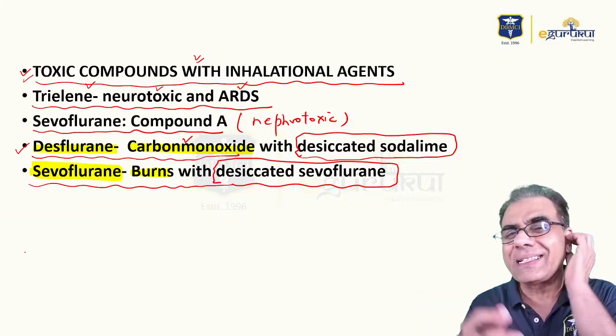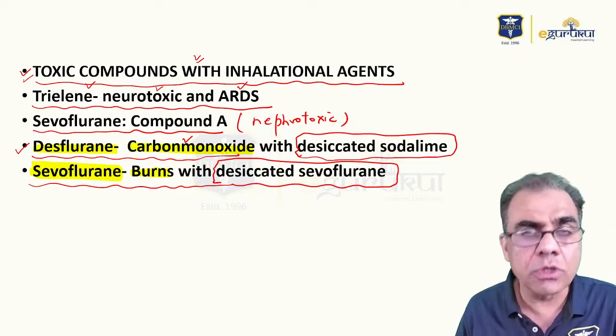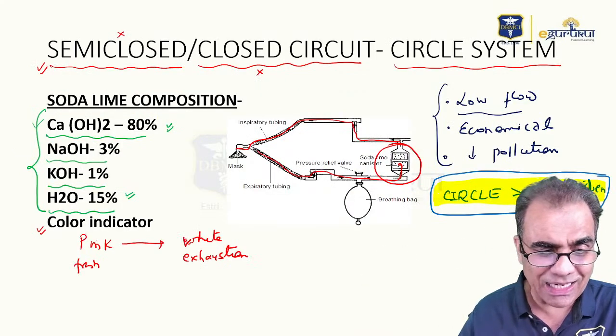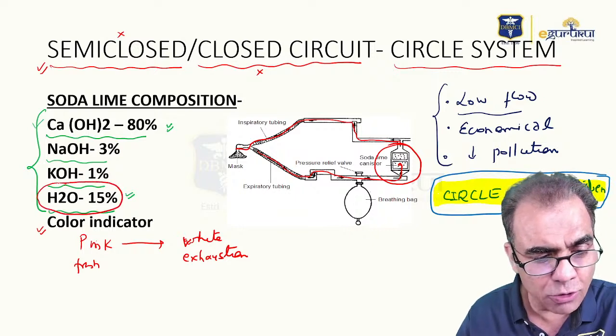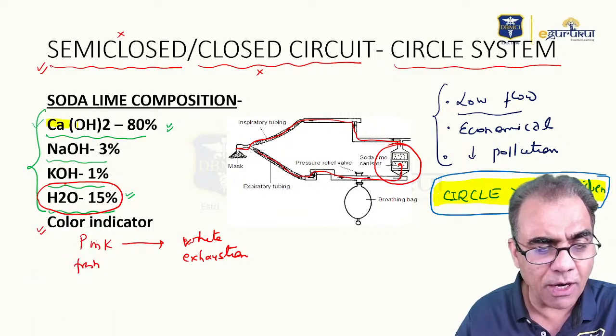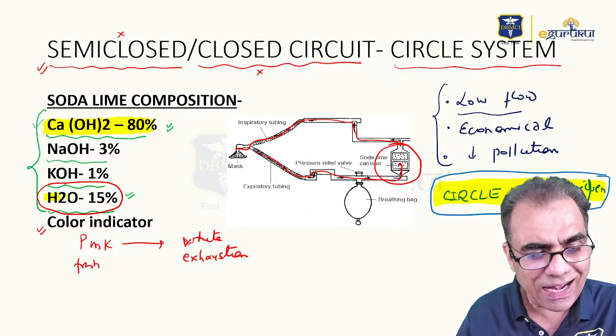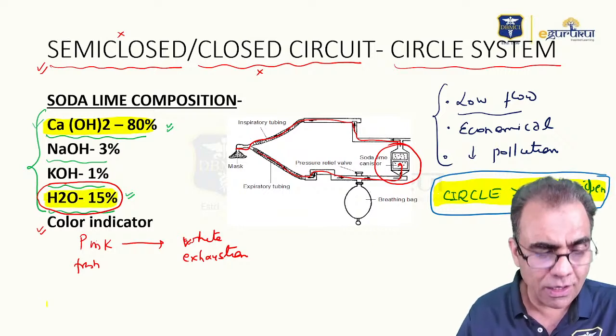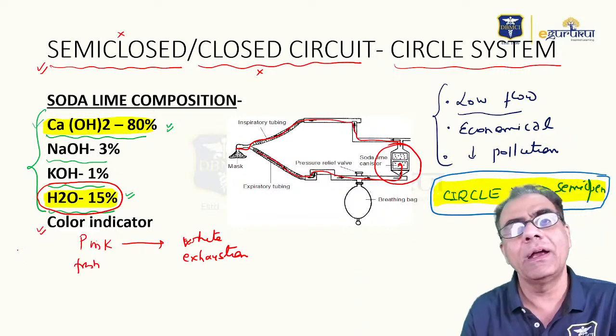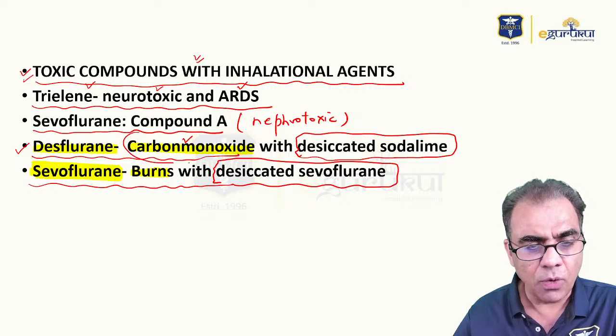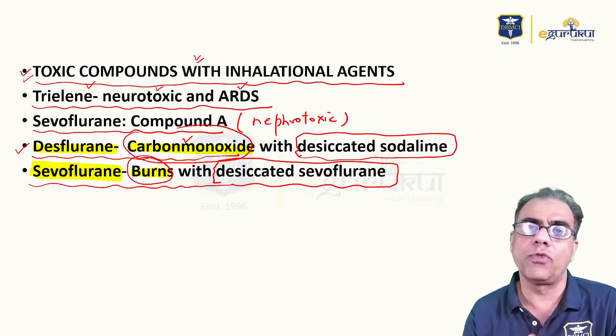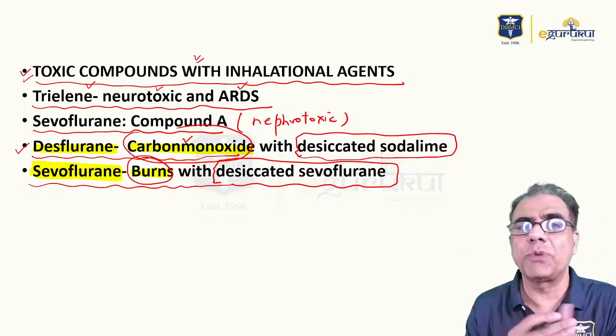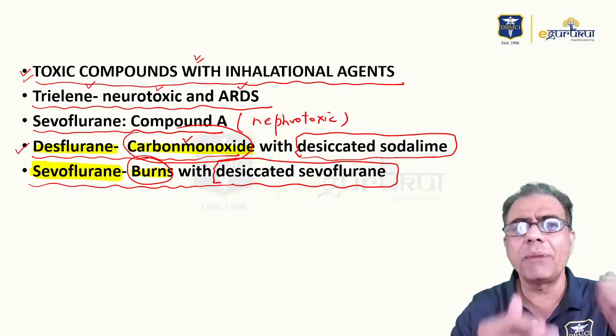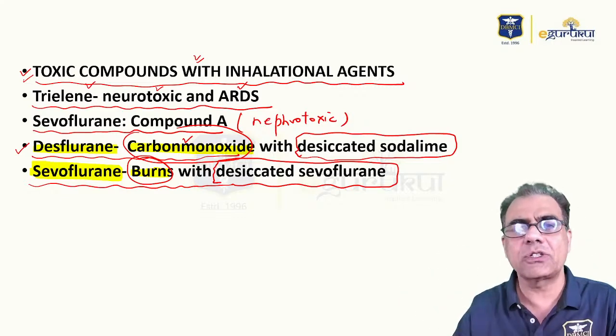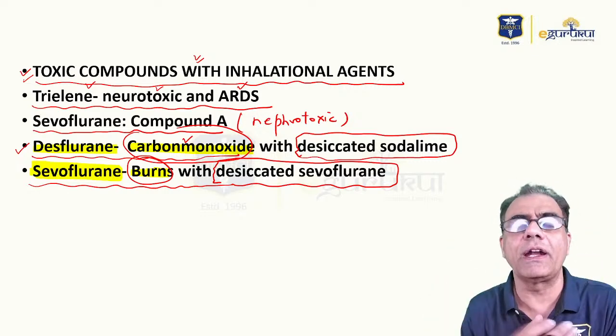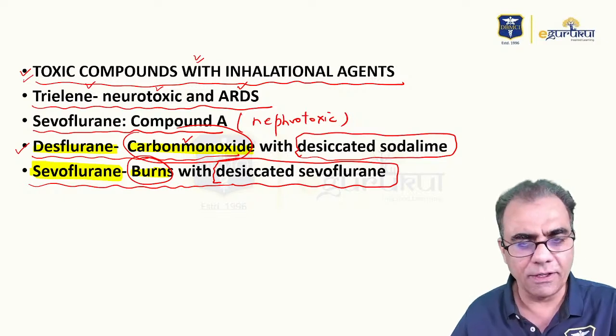reasons. One, when carbon dioxide reacts with soda lime, water is automatically produced, which prevents soda lime from getting desiccated. And second, as I told you, the latest available soda lime has reduced the calcium hydroxide from 95% to 80% and replaced it with water volume of 15% so that soda lime doesn't get desiccated, preventing dangerous complications like carbon monoxide poisoning with desflurane and burns of the respiratory tract with sevoflurane. So all these things are very latest because nowadays sevoflurane and desflurane are more commonly used. So what I'm trying to cover in this session is the latest topics on which you can have a very high possibility of getting questions.